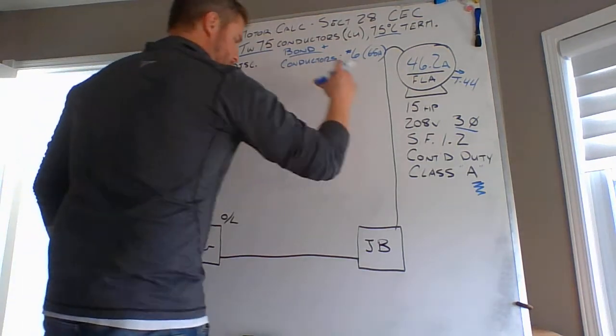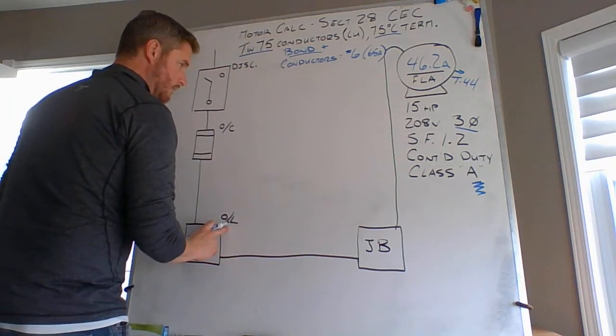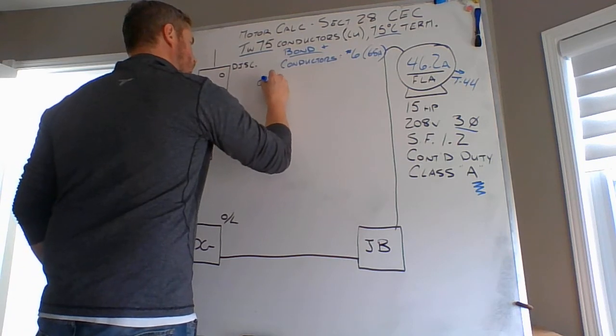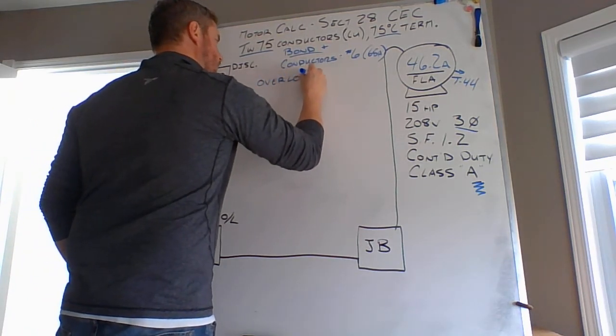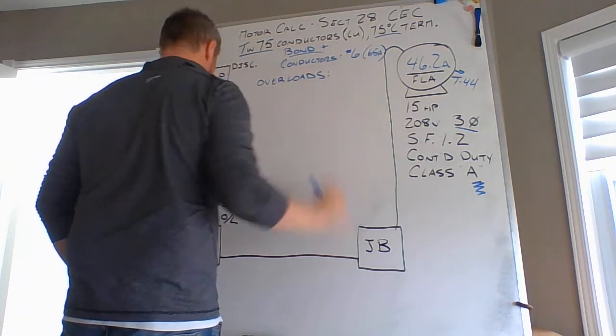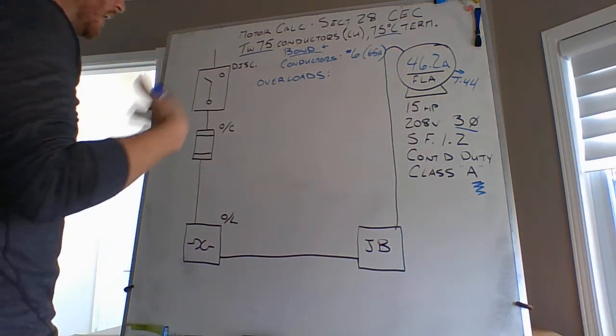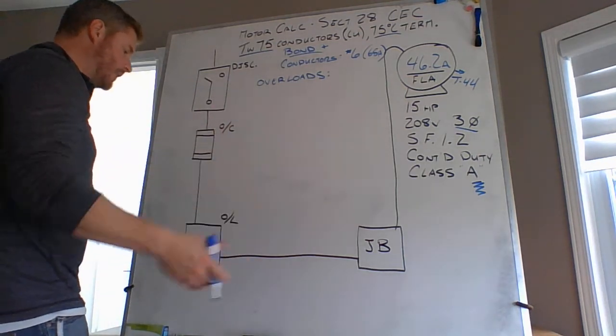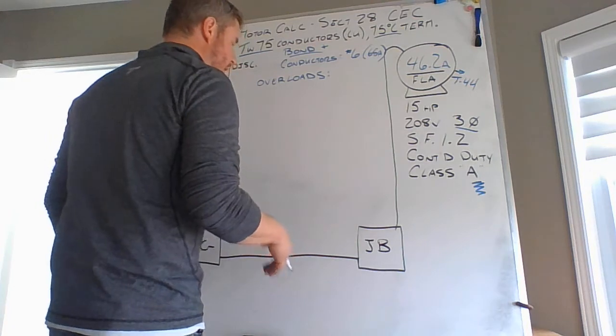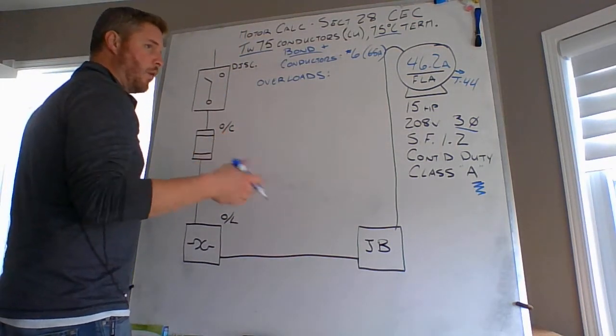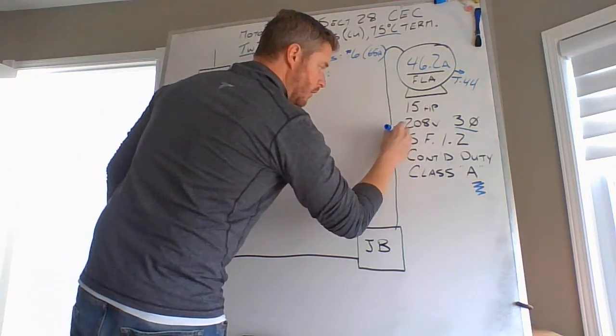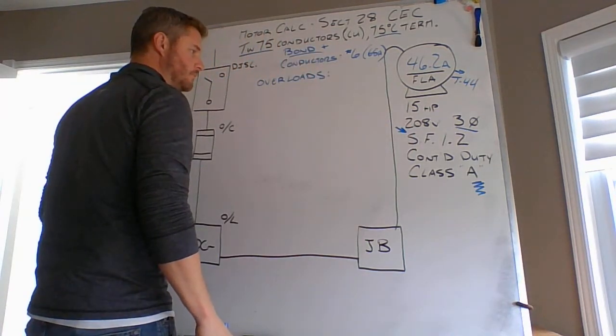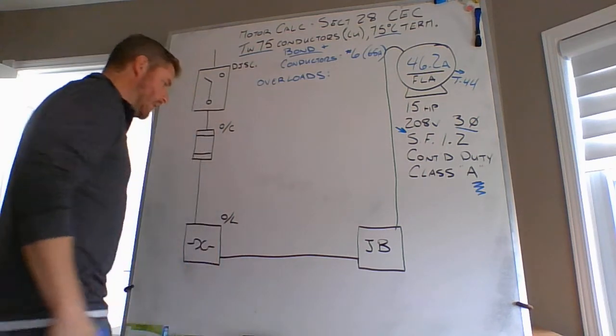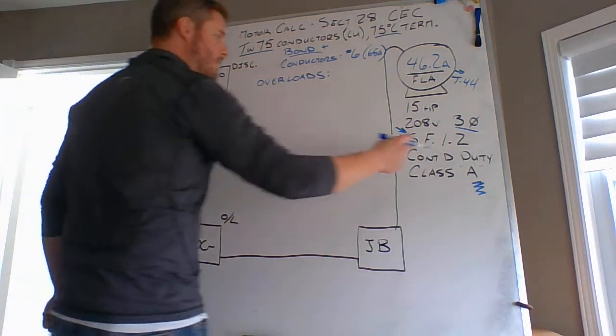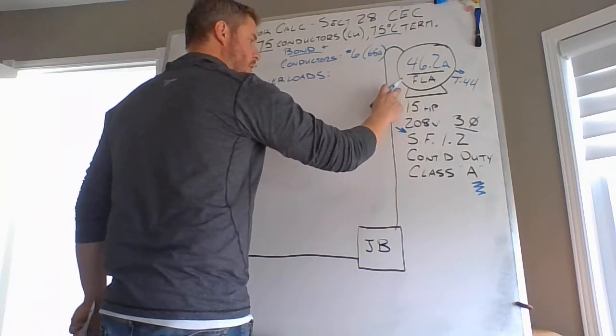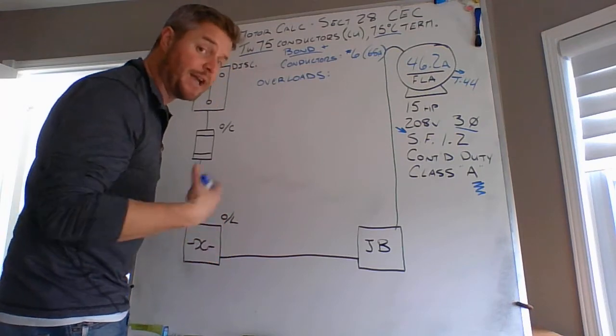The next portion that I would like to run through is your overload protection over here. Now, either with myself or Mr. Pratt, you've been connecting overload protection for all the motors that you've connected so far in installation methods. And that overload protection is set or rated at the service factor of that motor. So in this case, I'm operating at a 1.2 service factor for this motor. This means that it's a very trustworthy motor. I can trust this motor.